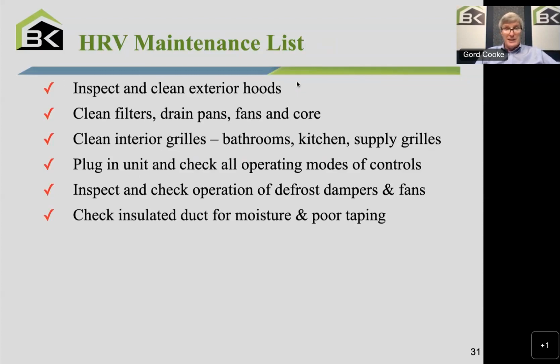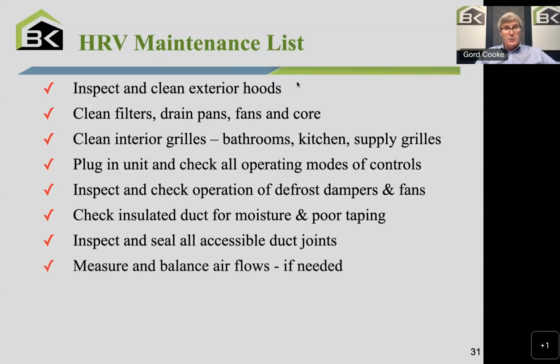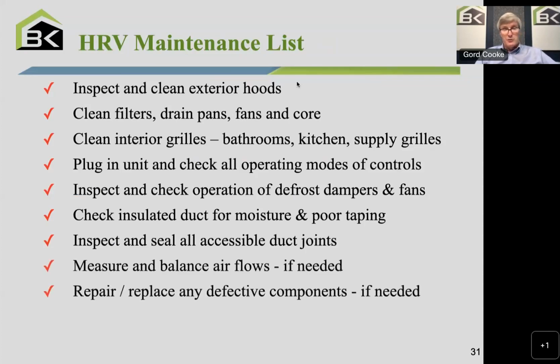We're going to check that insulated duct for moisture and poor taping to make sure there's no moisture in the duct. We're going to have a quick look at the ductwork to make sure all accessible joints are taped. If needed, we're going to measure and balance flows. If needed, we're going to repair and replace defective components. We're talking about maybe 20 to 30 minutes to clean hoods, filters, and cores: 3 times a year, the filters and the outside hoods; once a year, the core and maybe the drain lines. So not too bad in terms of the maintenance.